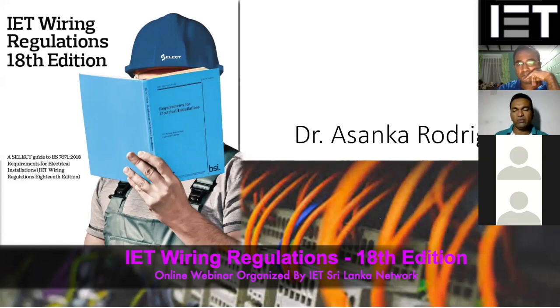That's why in the new standard they are not talking about any requirement for the TN installation, because if you have equipotential bonding, that fulfills your requirement. But when you look at lightning protection, IEC 62305 recommends having less than 10 ohms earth electrode resistance. So that is for any building. If you have a lightning protection system, if you are connecting your lightning protection system to the equipotential bonding, then you have to comply with that requirement.